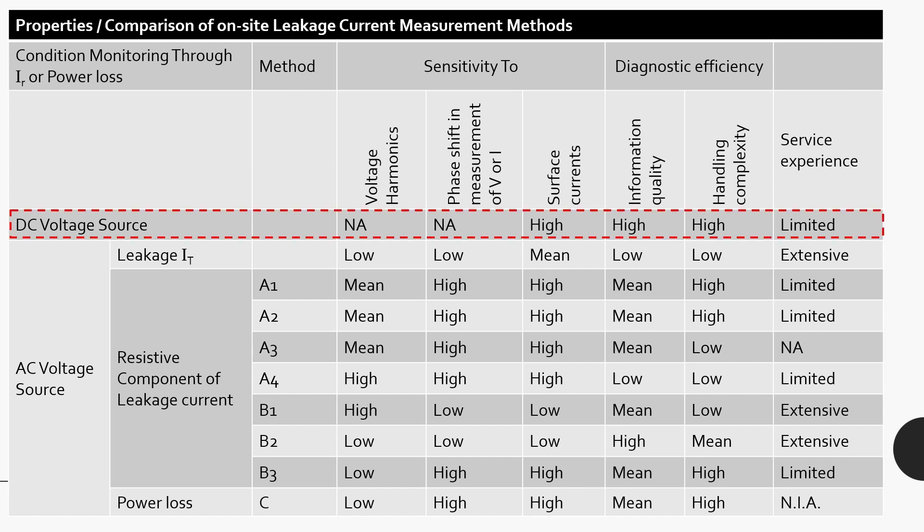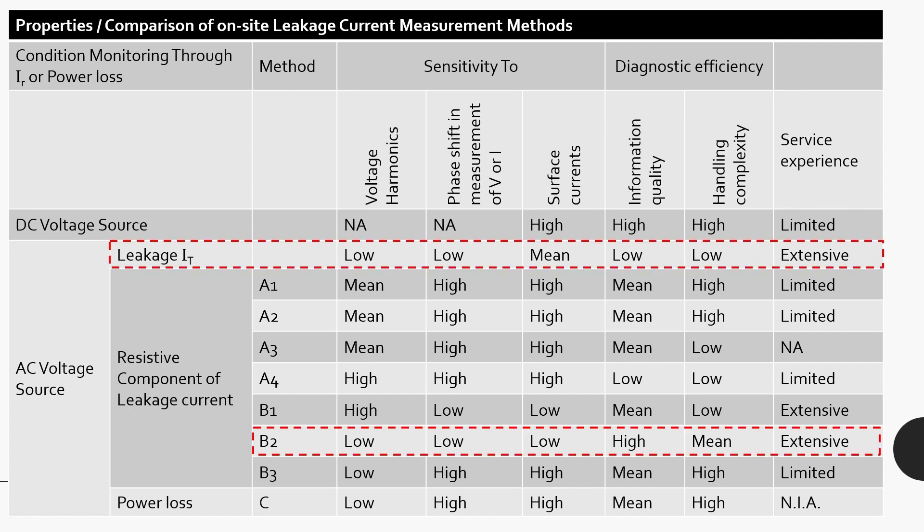Here you can find method of leakage current measurement using DC source. Yes, of course, DC source can be efficient in providing resistive leakage current measurement although the service experience is limited. Out of these, current measurement using leakage current meter and third harmonic leakage current measurement have very extensive site experience.